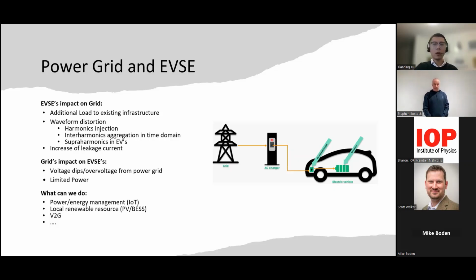There is something called supraharmonics, which means 2 kilohertz to 150 kilohertz. And nowadays, because all the chargers and the electric vehicles want to make the power electronics as small as possible, they start to increase the frequency. So all the devices are constantly switching at a very, very high frequency. That is where those supraharmonics could be generated and injected back to the grid.